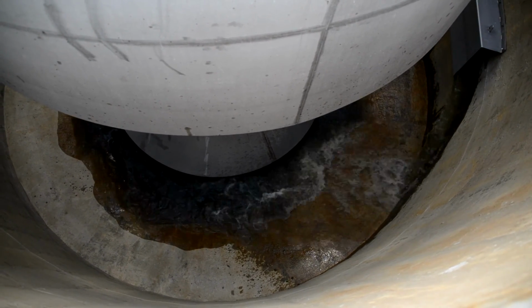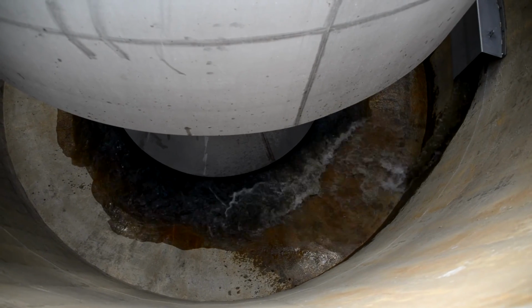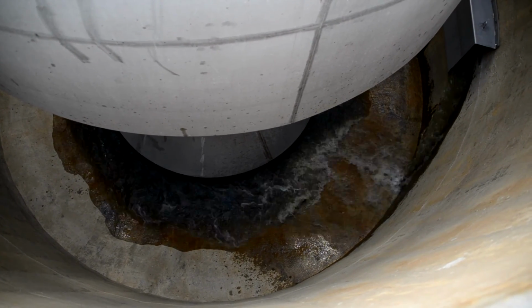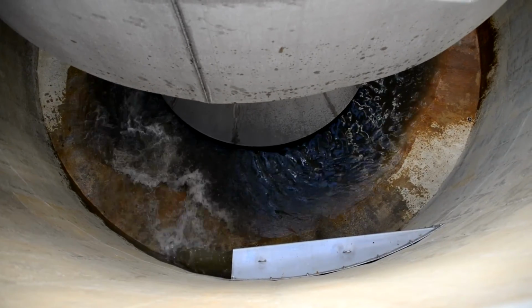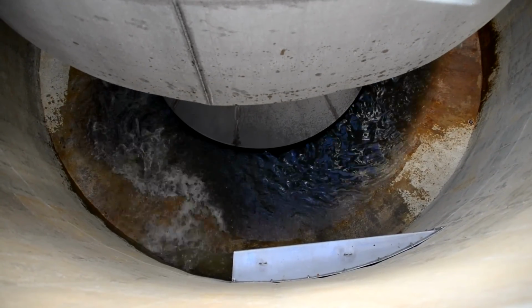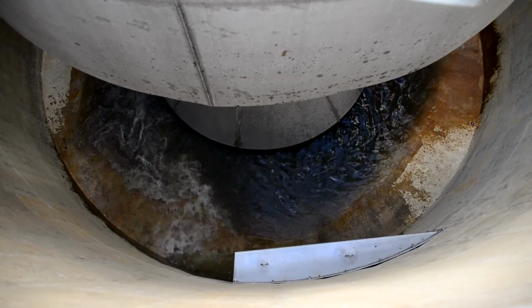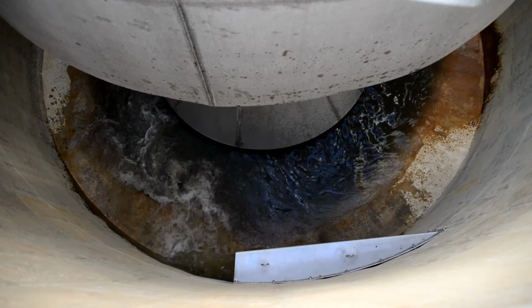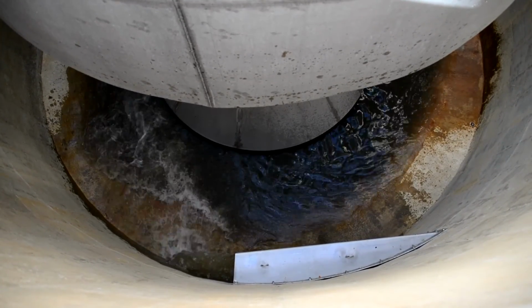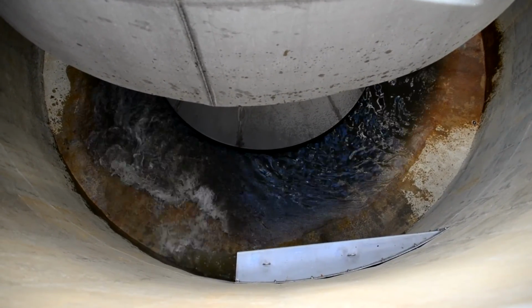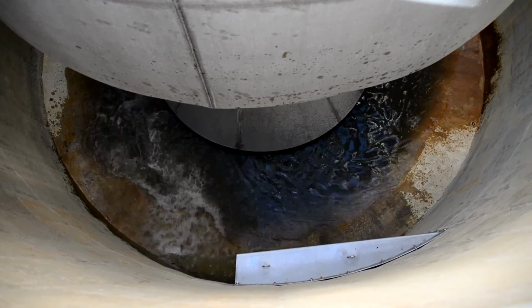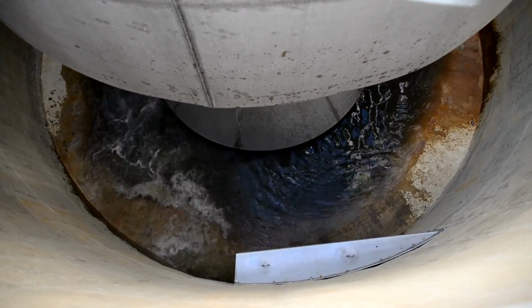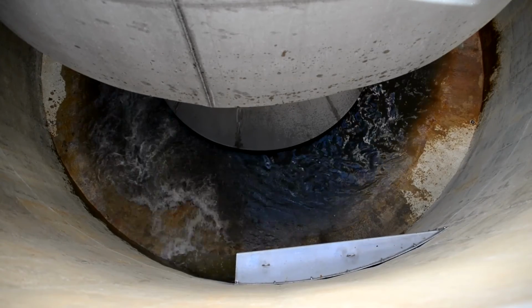The main flow is then directed away from the perimeter and back up the middle of the vessel as a narrower spiraling column rotating at a slower velocity than the outward downward flow. A dip plate is positioned on the underside of the support frame, which locates the interface between the outer downward circulation and the inner upward circulation. This area is called the shear zone, which allows for further separation.